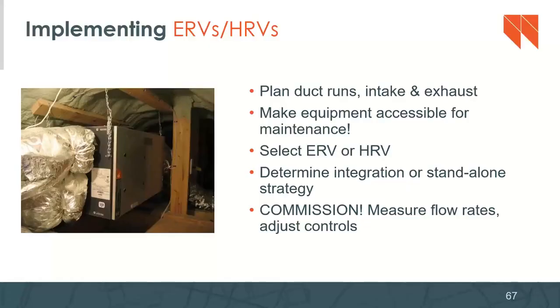Right, so how do we implement this stuff? These are the things that go into it. Plan the duct runs: where is the intake and the exhaust going to happen? Make the equipment accessible for maintenance. The ventilator is going to, at a minimum, need to have the filters changed. Usually on these ERVs and HRVs, every 3 months, really, the filter should be cleaned or changed. The manufacturer's suggested maintenance interval is going to change.